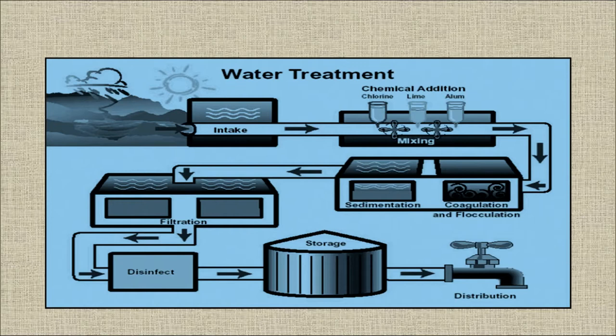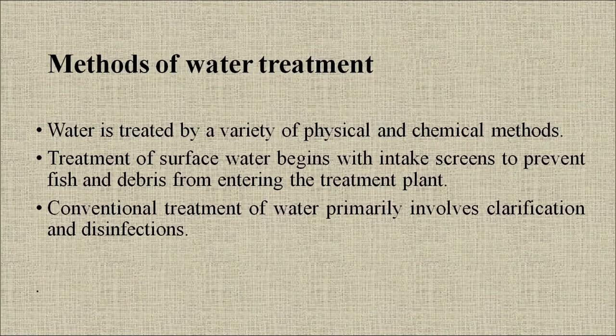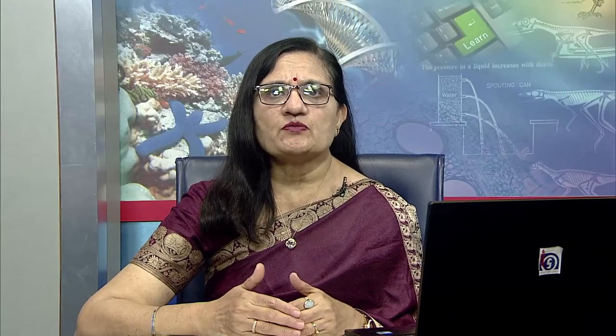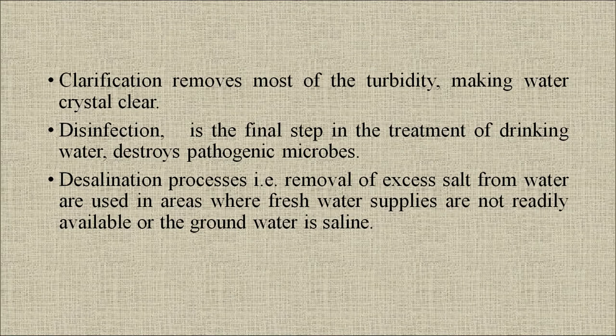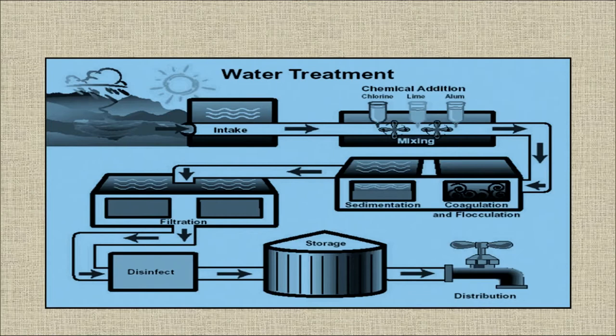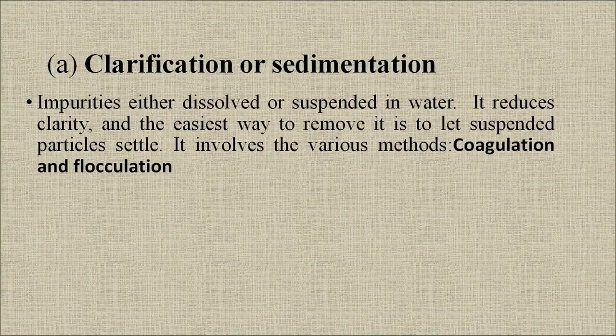Water is treated by a variety of physical and chemical methods. Treatment of surface water begins with intake screens to prevent fish and debris from entering the treatment plant. Conventional treatment primarily involves clarification and disinfection. Clarification removes most of the turbidity making water crystal clear, and disinfection removes pathogenic microbes. Desalination processes remove excess salt from water and are used in areas where fresh water supplies are not readily available or the groundwater is saline.